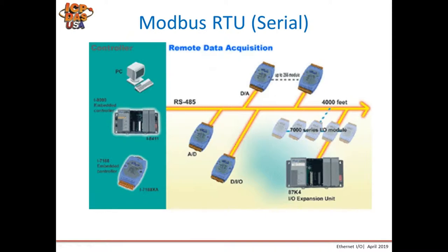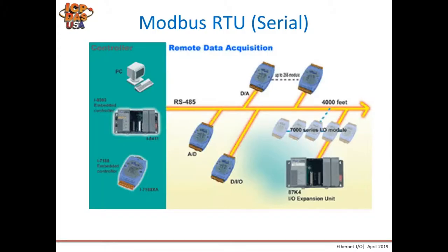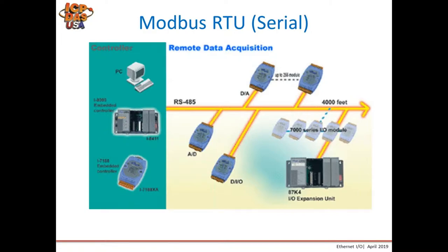Here's a typical schematic for a system using Modbus RTU. You have a serial master — note you can only have one master at a time talking to many RS-485 devices along a single RS-485 bus, up to 4,000 feet.